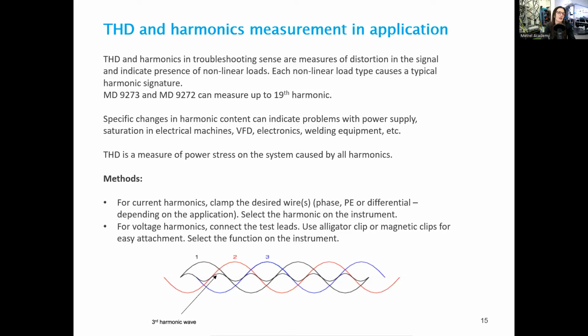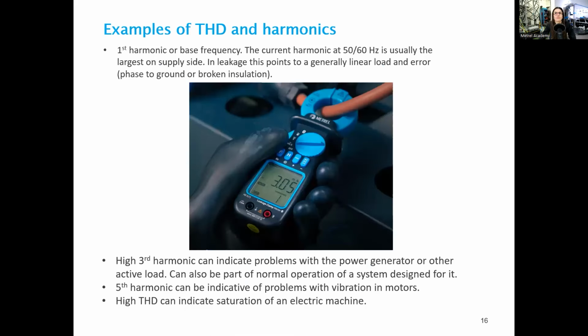Both MD9273 and MD9272 can measure up to the 19th harmonic for both current and voltage. The actual measurement is done by using the clamp jaw or the test leads to connect the instrument in the same way as for basic current or voltage measurement. So, some examples of using the harmonics and THD for troubleshooting.